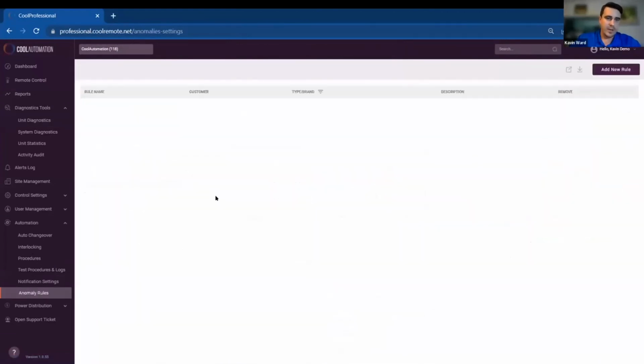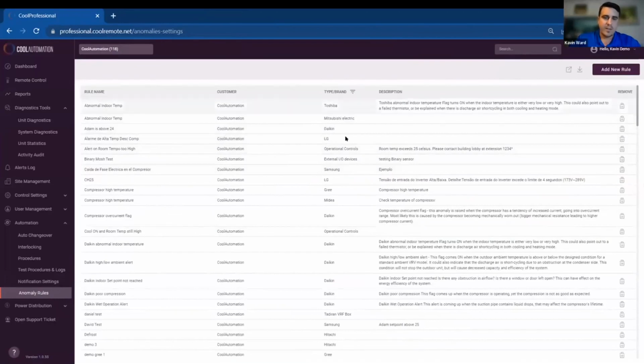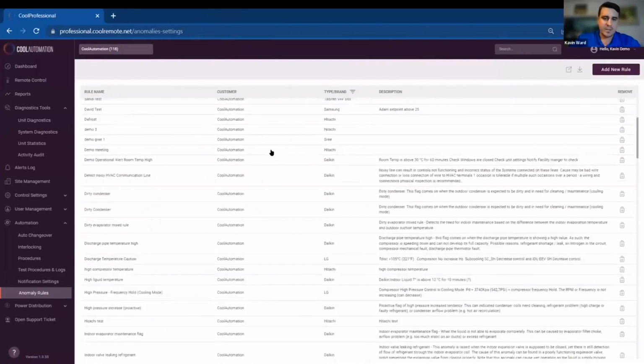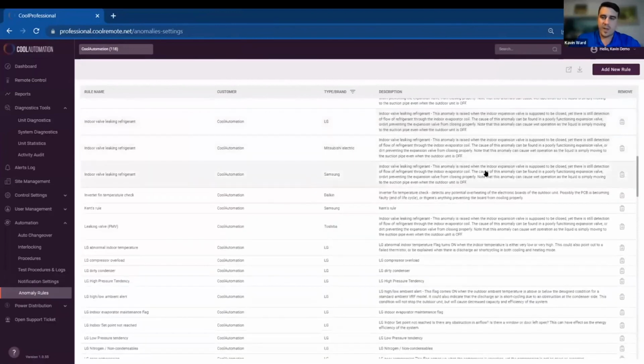So we can go to the anomaly rules section. We have a library set for Daikin, Mitsubishi, LG, Samsung. And of course, there is always the ability to customize any of the rules. And with these alerts, we'll be actively monitoring the performance of the system. When any of these factors are degrading your performance, of course, that incurs higher energy consumption. The system is not working as effectively as it can be because of some of the issues Ben has mentioned.